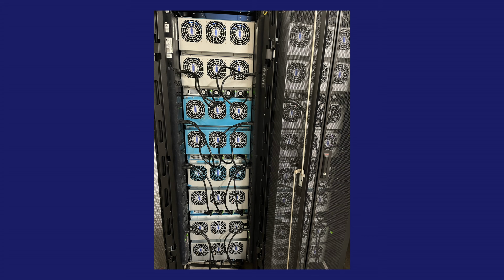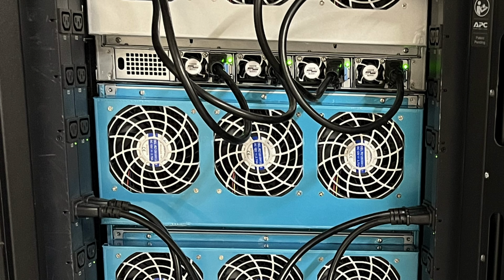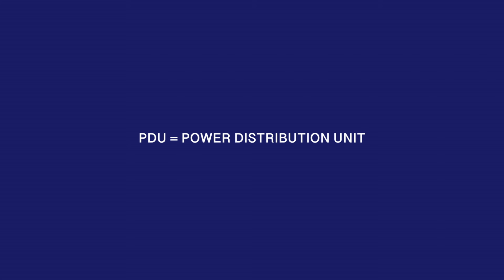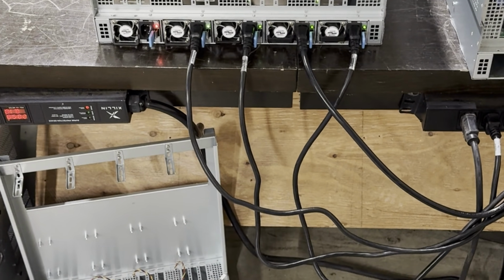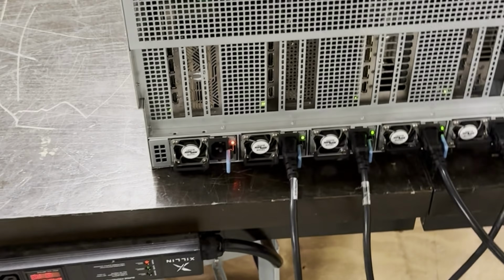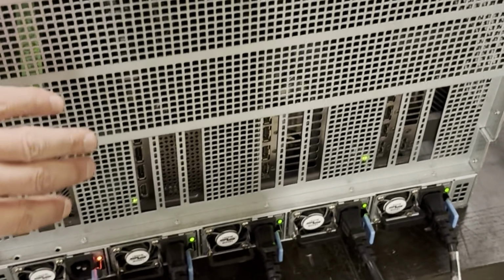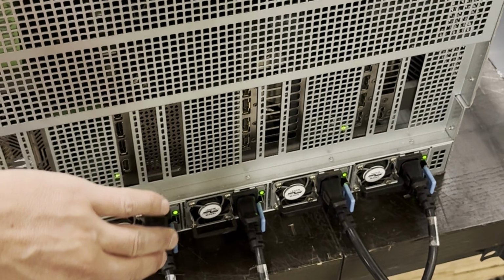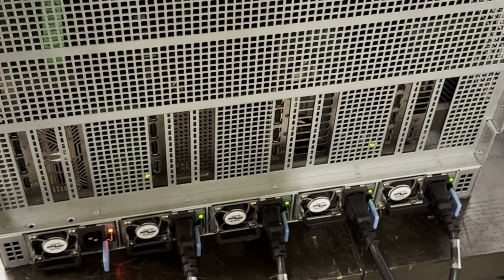But all in, we'd take 4 of these and put them all in a server rack. In the back of the rack, to power it, it made it really convenient because we would just use 4 0U vertical PDUs to distribute power. Each of those was 30 amp, 208 volt, and we could fit the 4 chassis with the PDUs in the back of the rack, each connected to one 1600 watt power supply in the back of each chassis. So each PDU powers one power supply on each chassis.